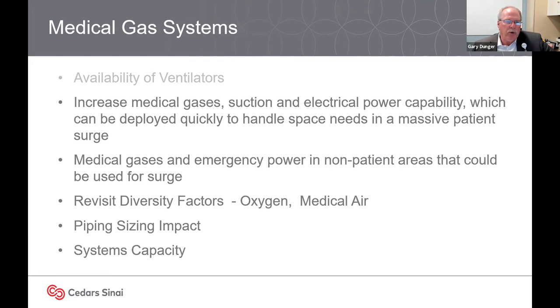But with the increased number of ventilators, there's obviously an increased demand for medical gas, suction, and electrical power capabilities in the rooms where ventilators are used. Those need to be designed in advance and put in place before the massive patient surge actually comes into fruition.